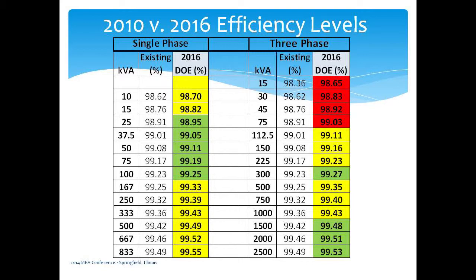Right now, a 15 kVA single phase is 98.76. Typically you'd think a three phase should be the same, since a three phase is really just three 15 kVA core coil assemblies. Sure enough, the existing 45 kVA is 98.76. Now look what happens when they make this change: the 15 kVA is bumped up to 98.82. So yes, the three phase should be 98.82, right? For a 45, it's 98.92.